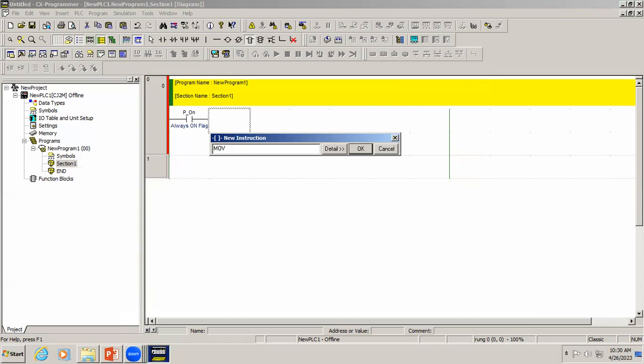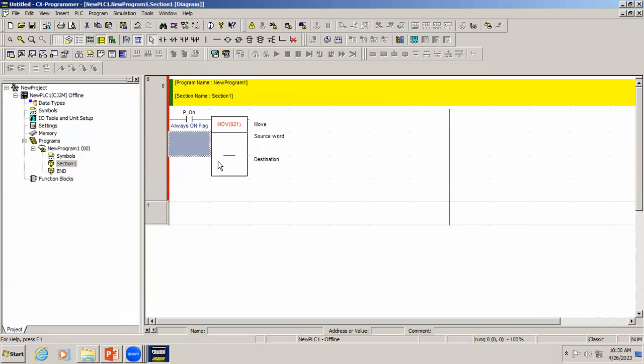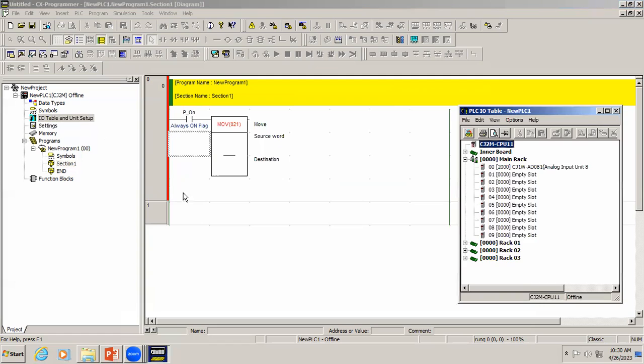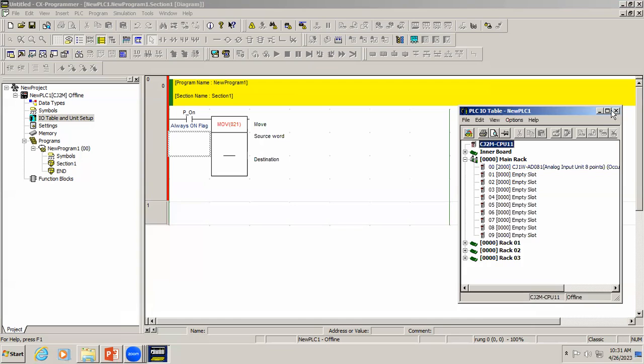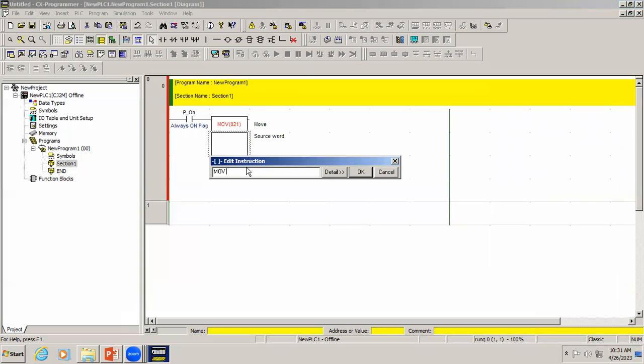We have connected one analog input device whose output is 0 to 10 volts, as we configured. The PLC is going to read that value, so we need to know the analog input address. In the I/O table hardware configuration you can see the address — since we are using the first input, the address is 2001. In the program I will use address 2001 and move whatever value is present at that input to register D0.